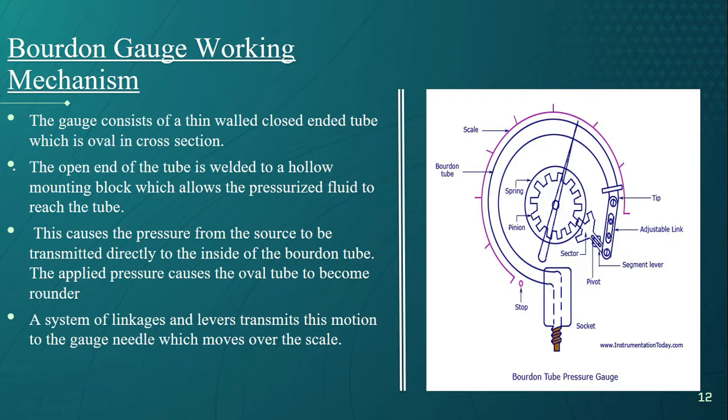This travel is suitably guided and amplified for the measurement of the internal pressure. The main requirement is that whenever the same pressure is applied, the movement of the tip should be the same and on withdrawal of pressure the tip should return to the initial point. A system of linkages and levers transmits this motion to the gauge needle which moves over the scale.